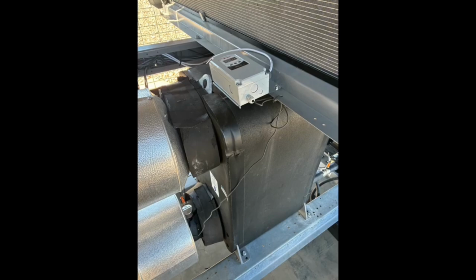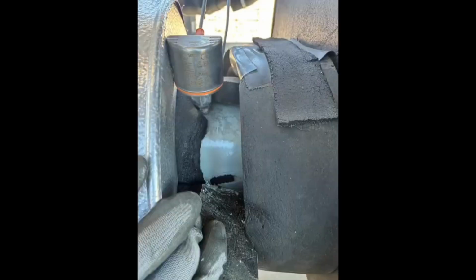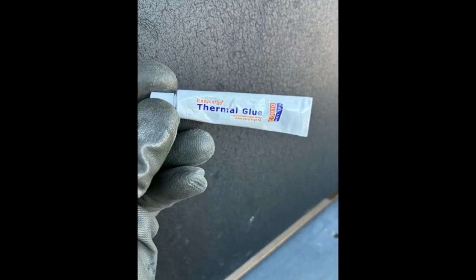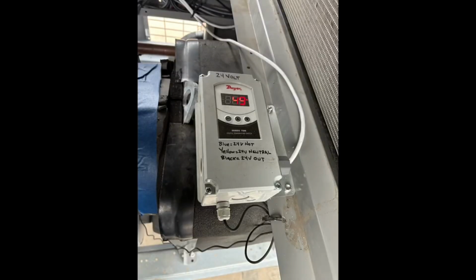You can see the temp probe comes down to the outlet pipe of the plate heat exchanger. I just sanded off some of the paint there. And I'm going to use this thermal glue to attach it and help improve thermal conductivity for accurate temp reading. That's what it looks like. Then I'll reattach the insulation, seal it up, power it up. You can see it's working, giving us an accurate temp reading.